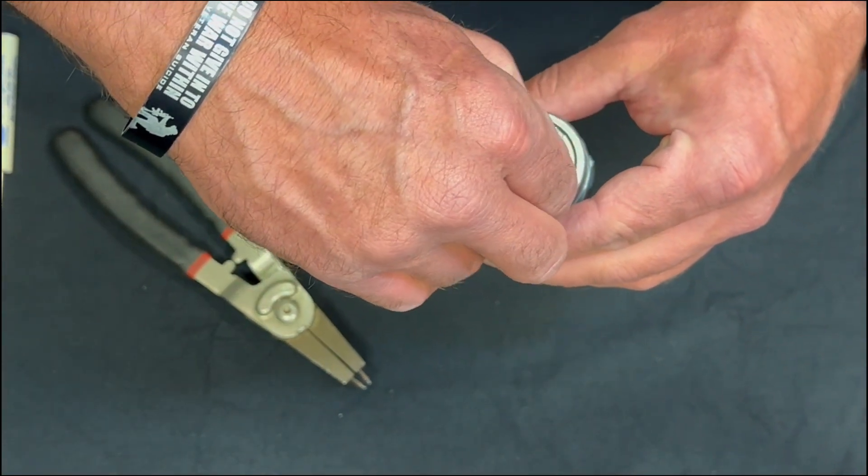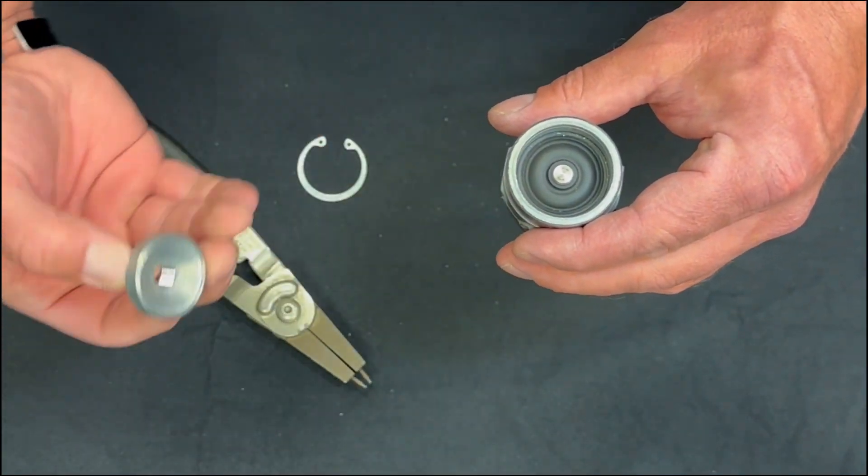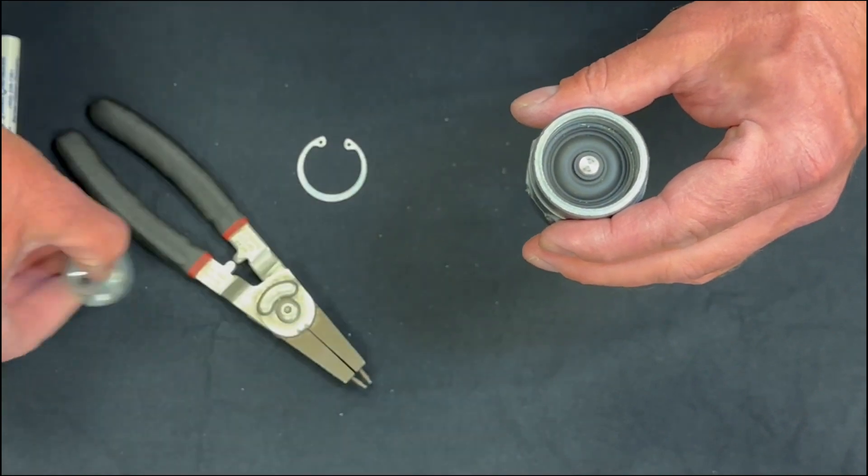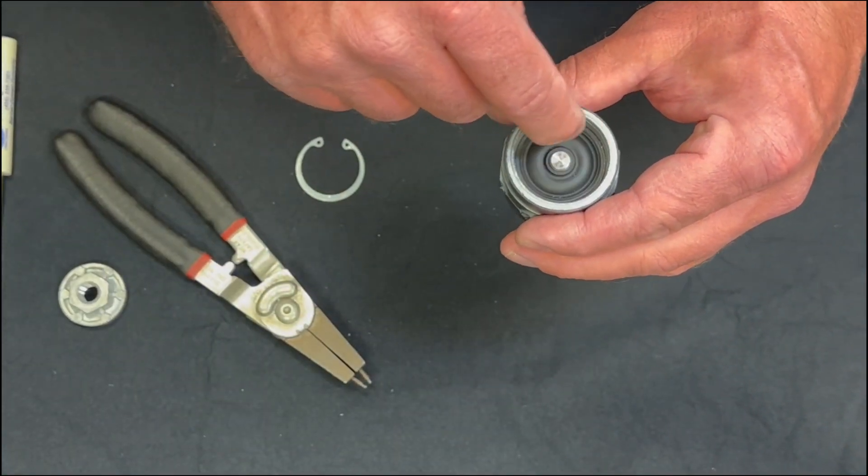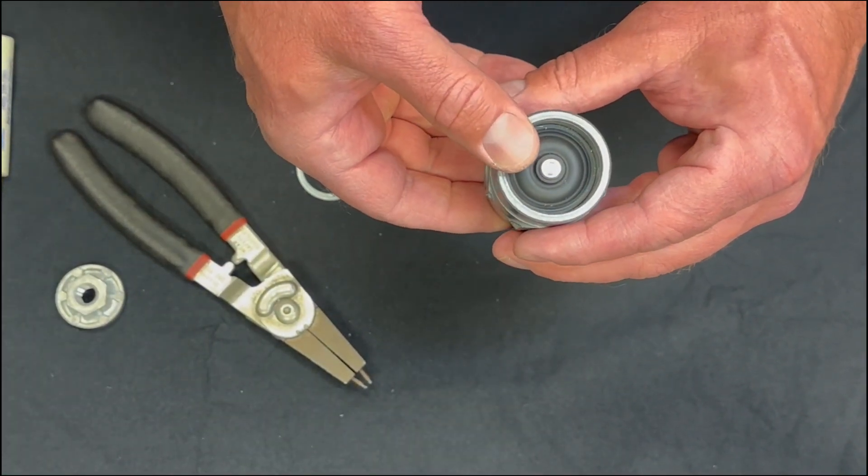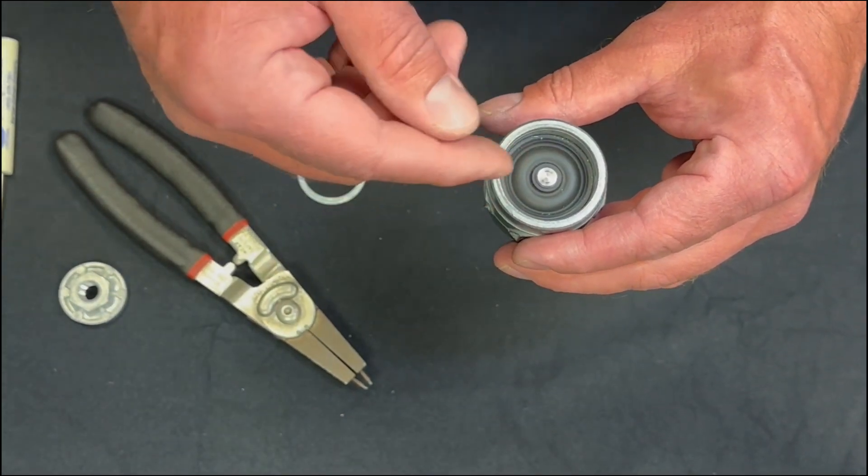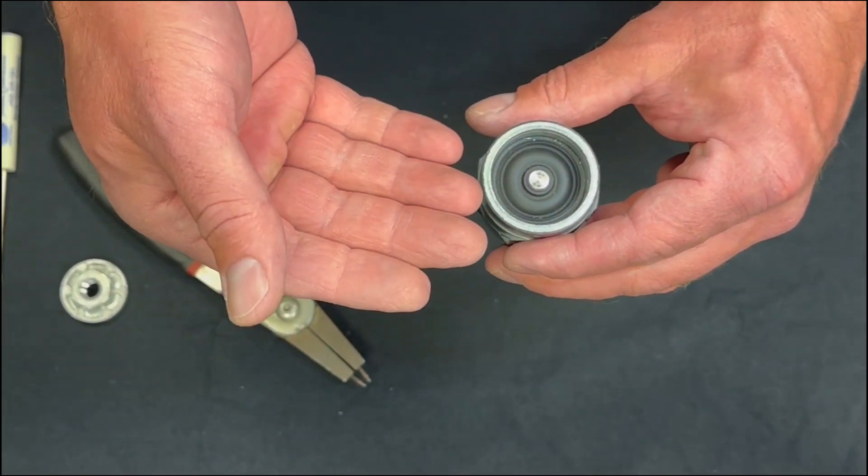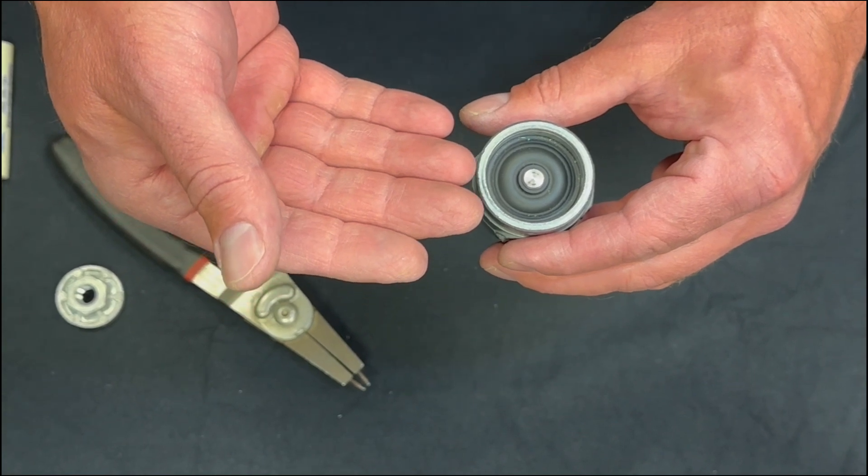Then you take the top cap of the diaphragm operated pilot valve, remove it, check for any scarring, and then you'll inspect the diaphragm of the pilot valve itself. You're going to be looking for tears, twisting, holes, or any kind of distortion that's going to cause the pilot valve to malfunction.